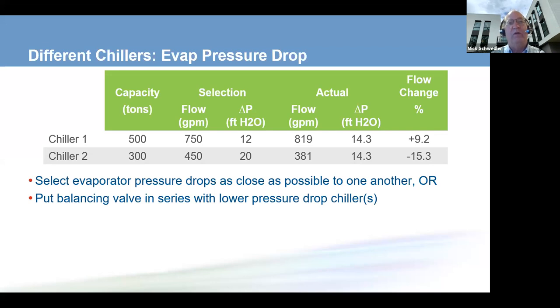So what you need to do if you have a system like this is, if you can, select the evaporator pressure drops as close to one another as possible. If you can't get it close enough, you will need to put a balancing valve in series with this chiller, one that has the lower pressure drop, to bring its pressure drop up to the same pressure drop as chiller two had.